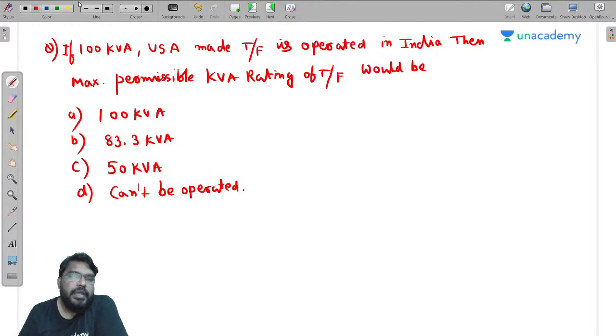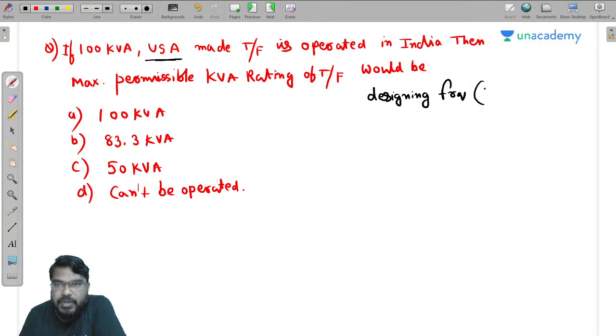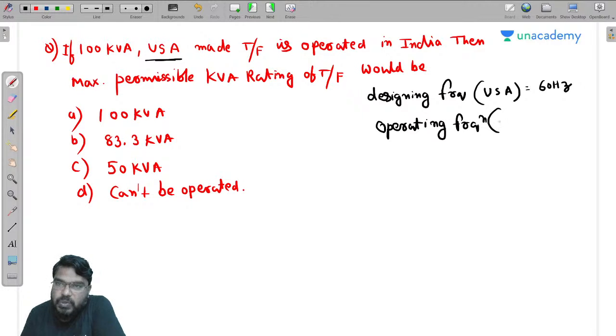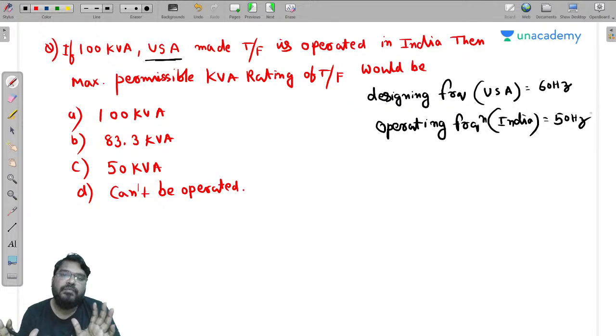Okay, like this. Any electrical machine can be operated below its rated value. Here it is made in the USA, so that means the designing frequency of the transformer is 60 Hz. And the operating frequency, since it is operated in India, is 50 Hz. Got it my point? Any electrical machine can be operated below its rated value, but it cannot be operated above its rated value.